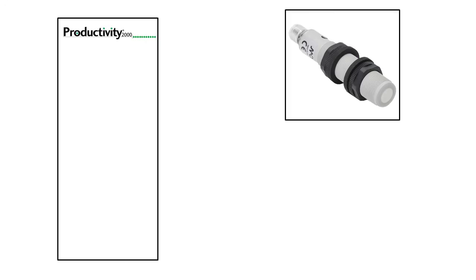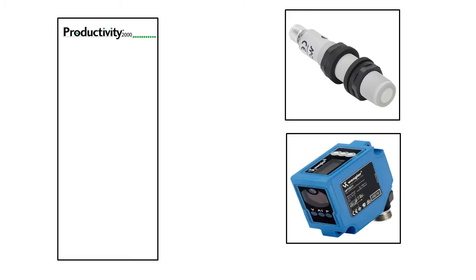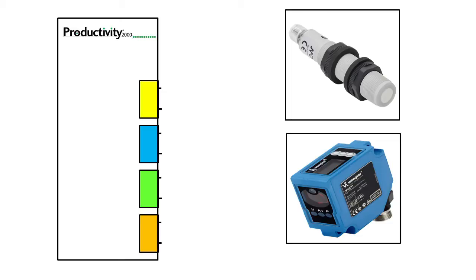Since we only have one current and one voltage input, we use the least expensive option – the single 4 channel module. The cool thing about this module is you can set each channel to either current or voltage. You don't have to dedicate the entire module to one or the other.